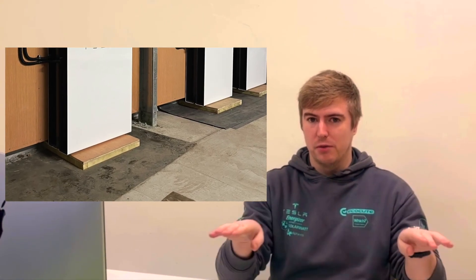We've had to walk around the job and there are a couple of challenges to overcome. The first challenge is when we install the stacking kit, you need the ground completely level. So as Corey said, we're going to build little platforms to make every single Powerwall level so the Powerwalls sit upon the platform and then get joined to the first Powerwalls.